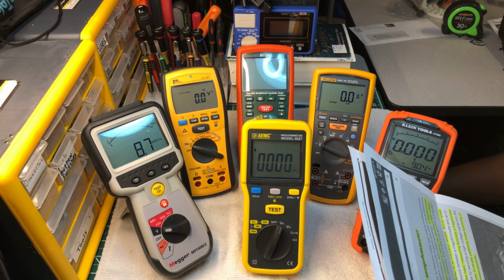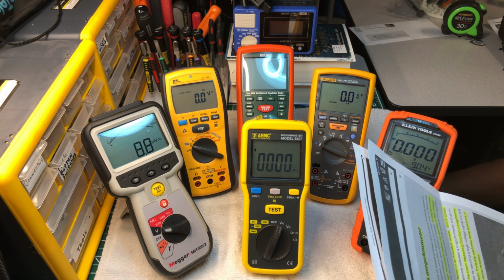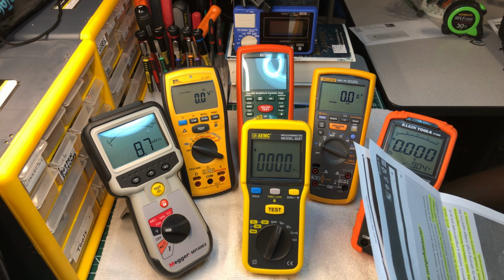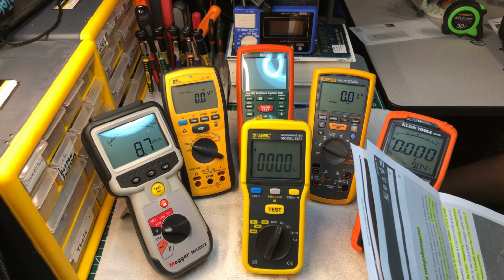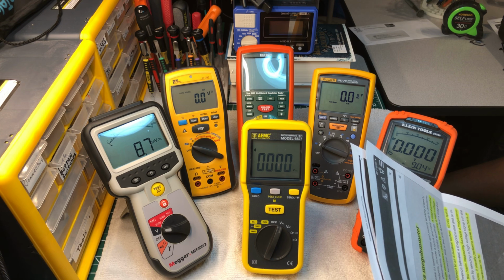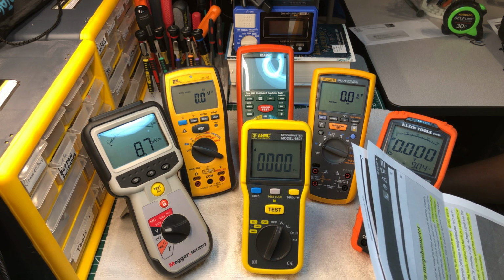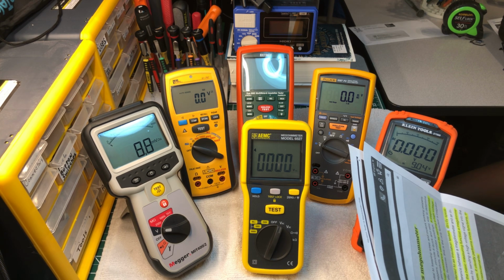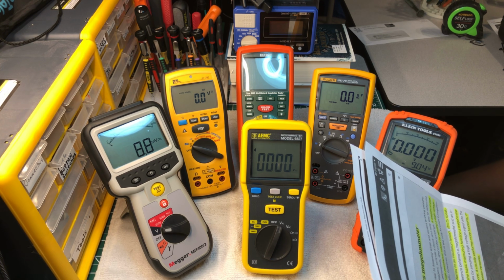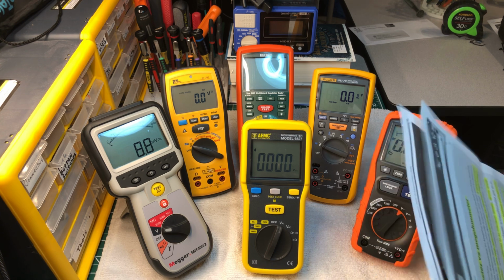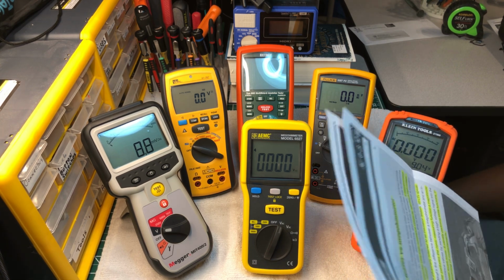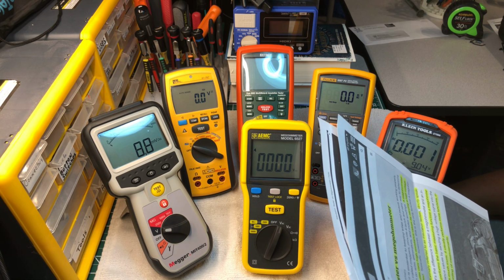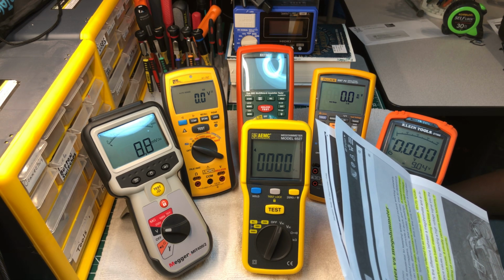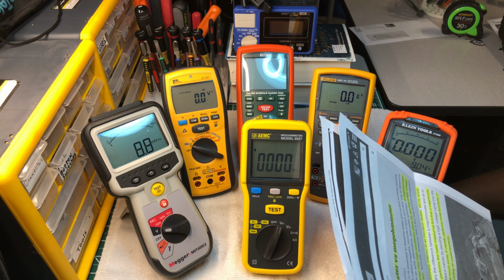I knew that already. Megohmmeters, sometimes called meggers, provide a quick and easy way to determine the condition of the insulation on wire, generators, and motor windings. A megohmmeter is an electric meter that measures very high resistance values by sending a high voltage signal into the object being tested. Typically, however, this is the only function a megohmmeter performs. While megohmmeters are often informally referred to as insulation testers, strictly speaking, this is not accurate.